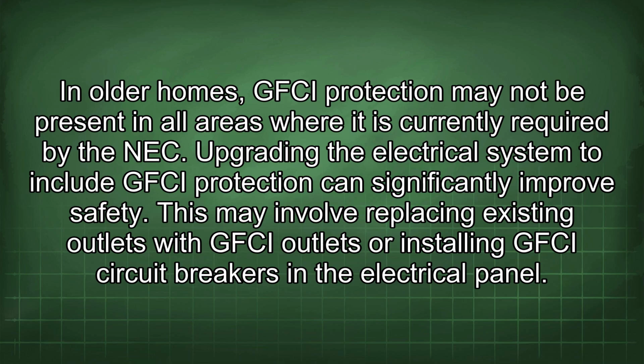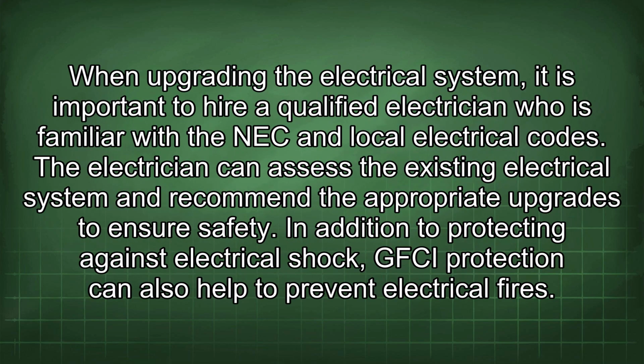In older homes, GFCI protection may not be present in all areas where it is currently required by the NEC. Upgrading the electrical system to include GFCI protection can significantly improve safety. This may involve replacing existing outlets with GFCI outlets or installing GFCI circuit breakers in the electrical panel. When upgrading the electrical system, it is important to hire a qualified electrician who is familiar with the NEC and local electrical codes. The electrician can assess the existing electrical system and recommend the appropriate upgrades to ensure safety.